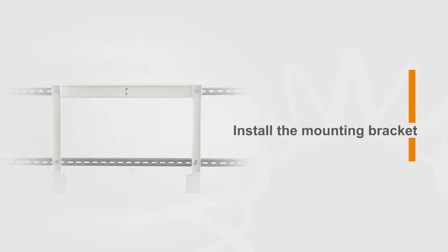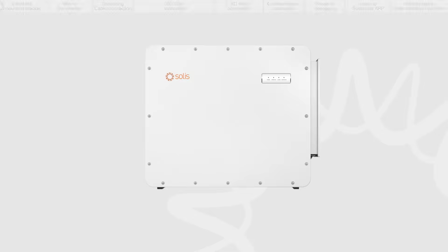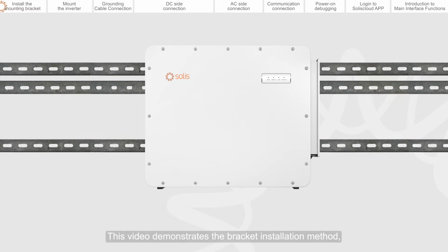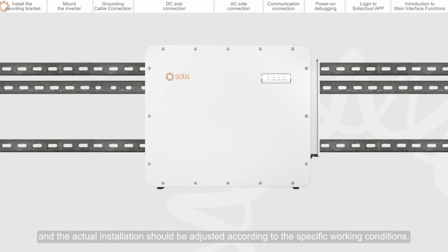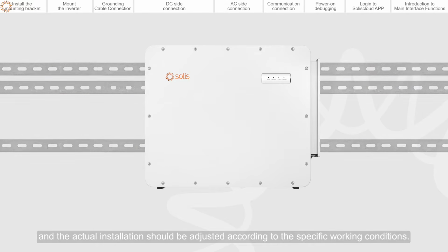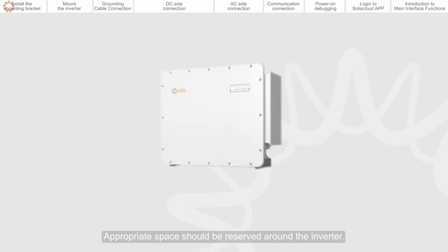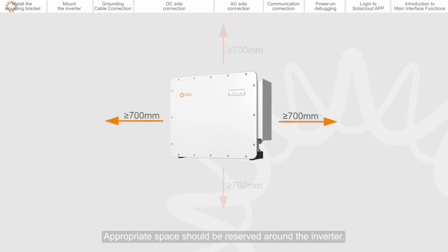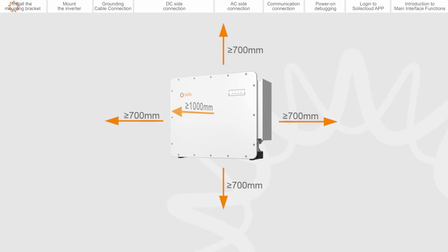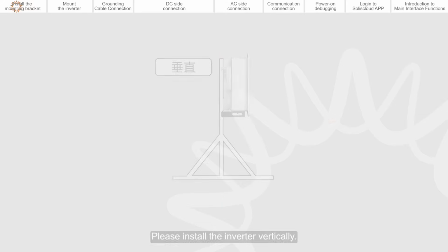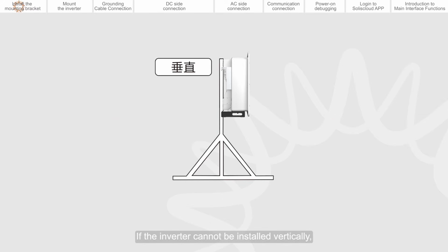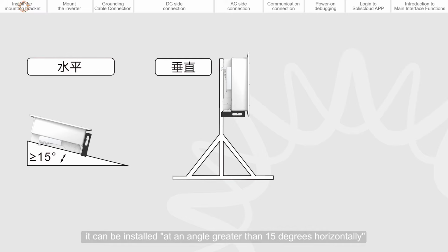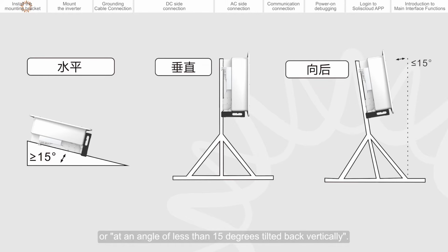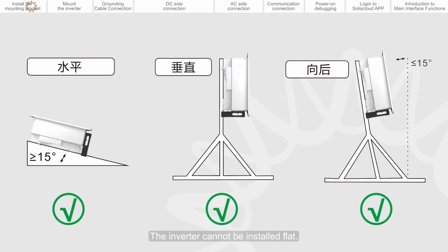Install the mounting bracket. This video demonstrates the bracket installation method, and the actual installation should be adjusted according to the specific working conditions. Appropriate space should be reserved around the inverter. Please install the inverter vertically. If the inverter cannot be installed vertically, it can be installed at an angle greater than 15 degrees horizontally, or at an angle of less than 15 degrees tilted back vertically. The inverter cannot be installed flat.